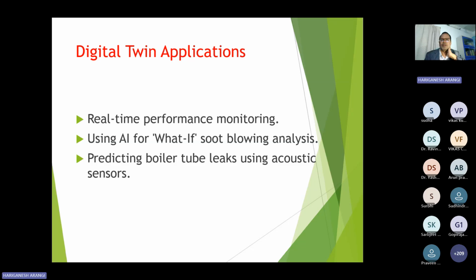And there is real-time performance monitoring, using AI for soot blowing systems and predicting boiler tube leakages using acoustic sensors. When a boiler tube leaks while running, people will not come to know whether it is leaking or not until the leakage becomes significant. These acoustic sensors will give the difference in noise when the water leaks. By these sensors we can also minimize major failures in the boiler.